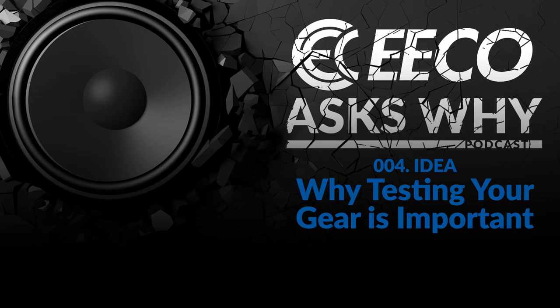And that is a podcast unto itself. I'll just say that. Trip functions within trip units might be a great topic for somebody a little bit brighter than me. But what you're going to do is run that trip unit through its long time, its short time, and its instantaneous, and perhaps its ground fault protection schemes, and make sure that it, as a trip unit, is sending signals to the breaker to actually open and close properly.